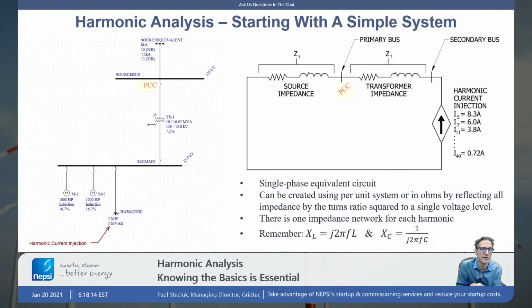We have a source bus. We have this thing called PCC. This is a concept that's utilized with the IEEE, and it's called the point of common coupling. It's really the interconnect. It's where the harmonic standards are applied for interconnection to a utility grid. If you're, say, a utility customer, an electrical, petrochemical plant, or a mine, for instance, or a renewables plant.